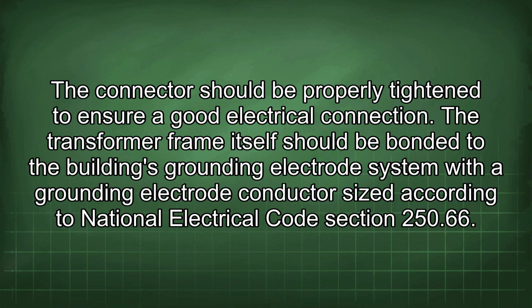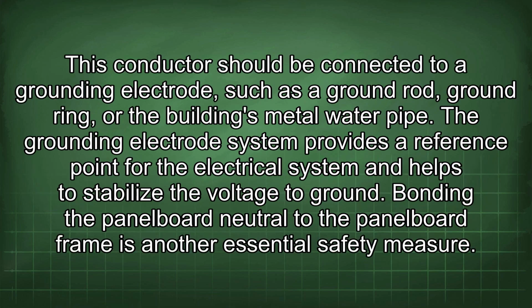The transformer frame itself should be bonded to the building's grounding electrode system with a grounding electrode conductor sized according to National Electrical Code Section 250.66. This conductor should be connected to a grounding electrode, such as a ground rod, ground ring, or the building's metal water pipe. The grounding electrode system provides a reference point for the electrical system and helps to stabilize the voltage to ground. Bonding the panel board neutral to the panel board frame is another essential safety measure.